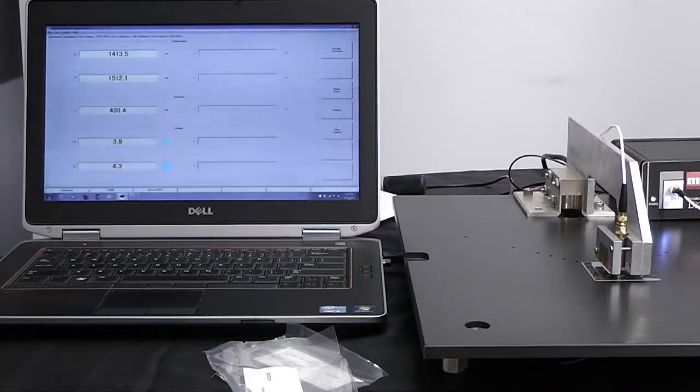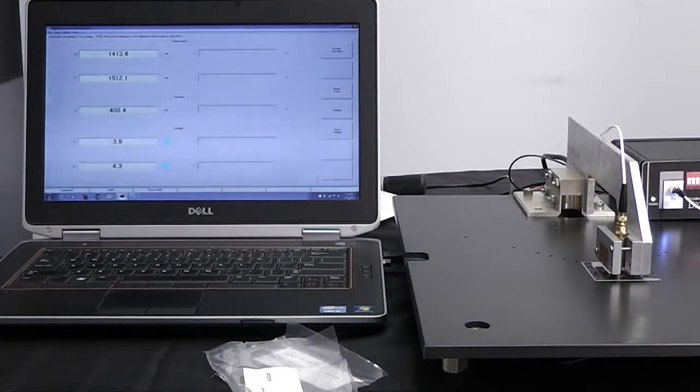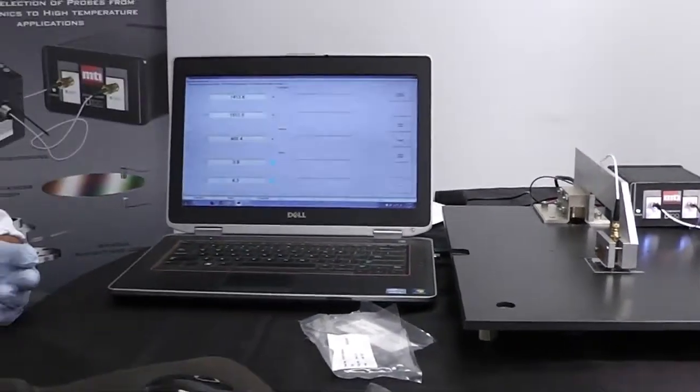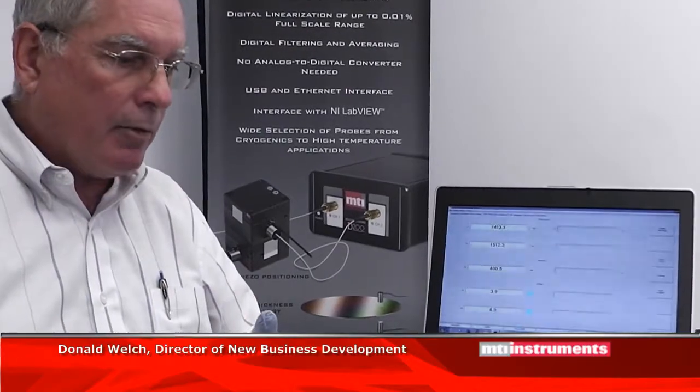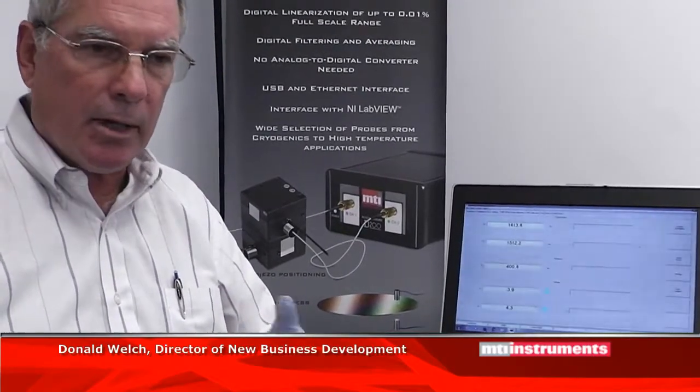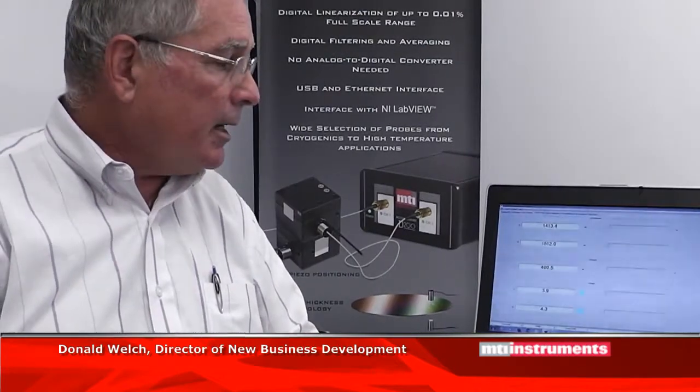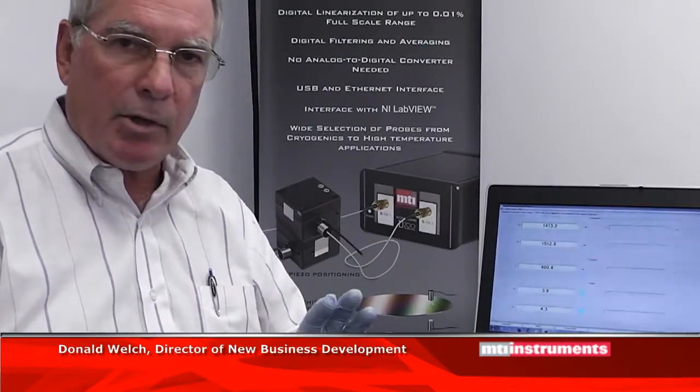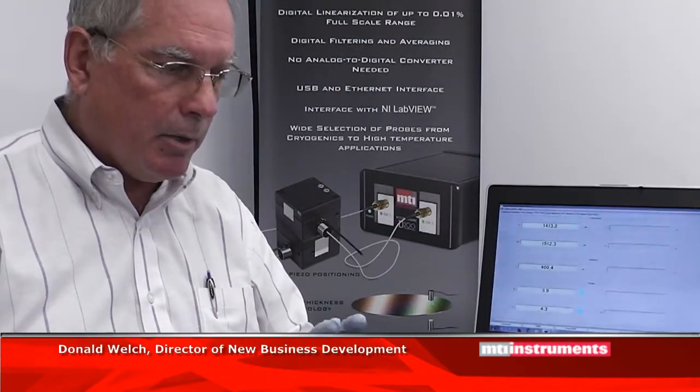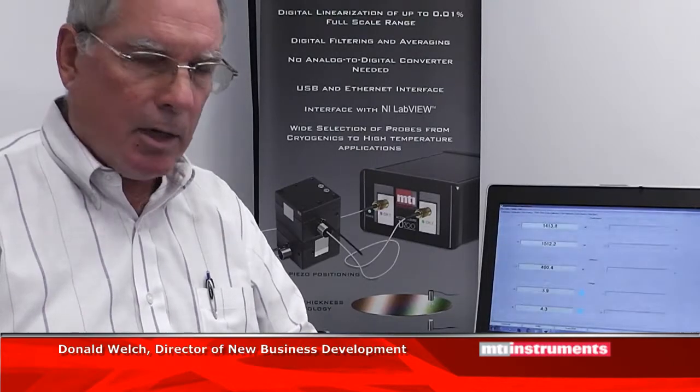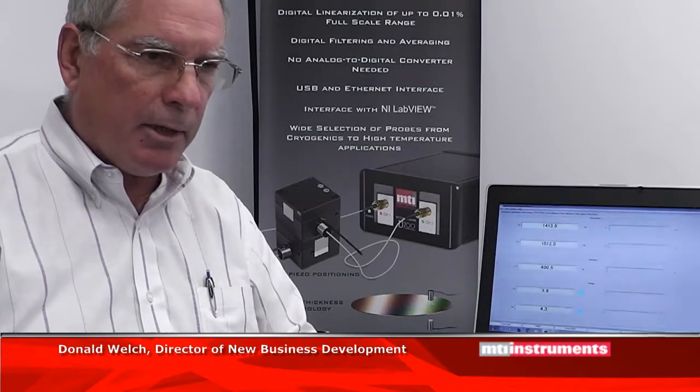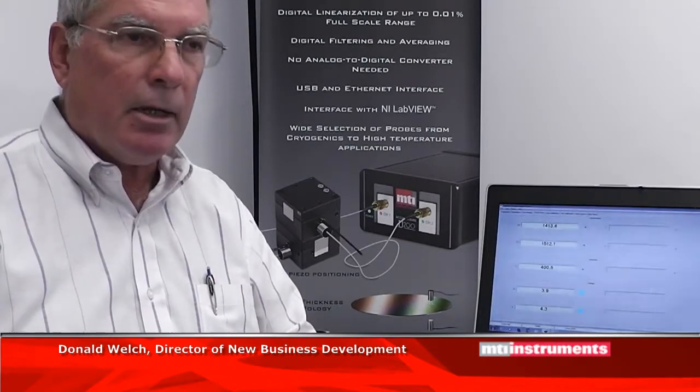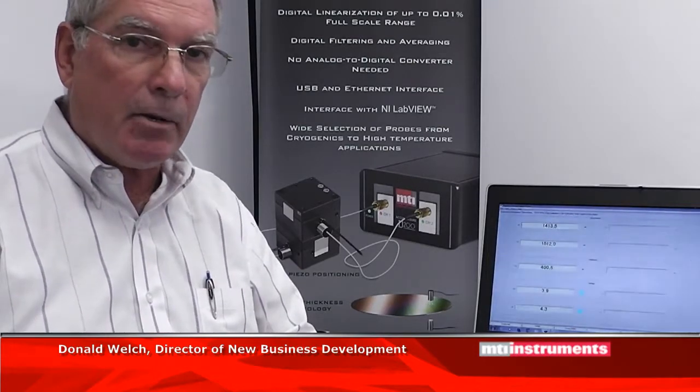So, what we've seen here in this tutorial is that we can measure a variety of different non-conductive materials such as sapphire wafers, plastic, which could be in process, and we've also looked at Gorilla Glass, which is a dielectric and non-conductive material. And we get very good accuracy with what we're seeing here. It's within 2 to 3 microns of what it's supposed to be. And if you're very careful with the cleanliness and setup, you can get down to typical accuracies of less than a micron.